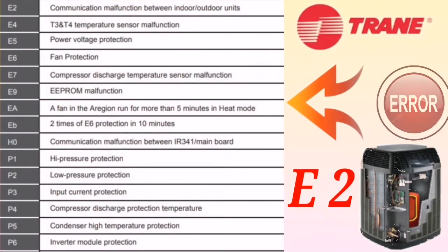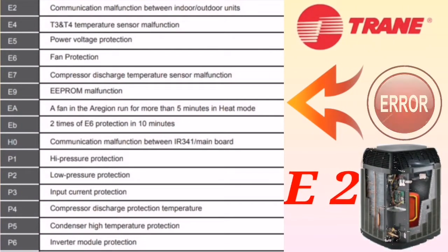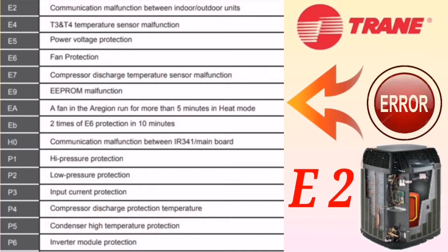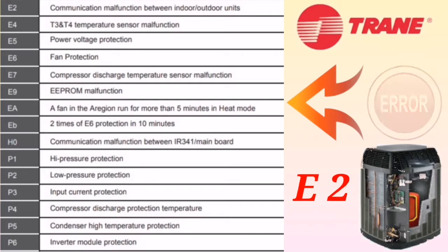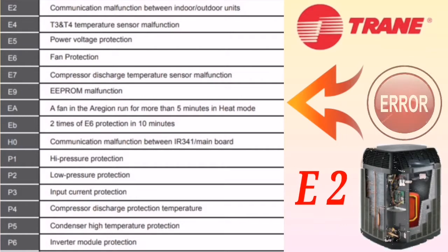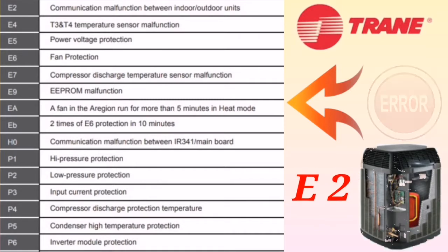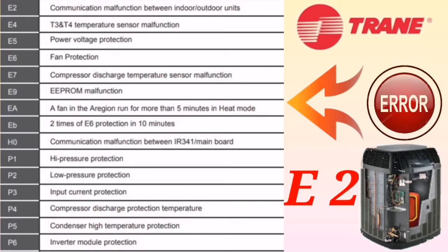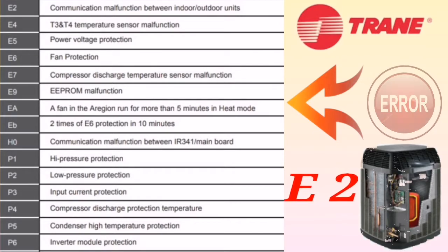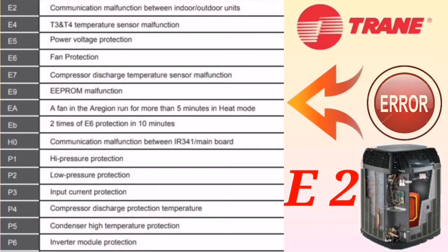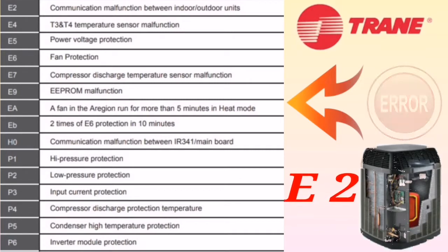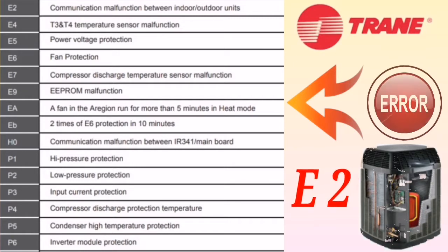The first error code is E2, which means communication malfunctioning between indoor and outdoor unit. First, check the communication cable between indoor and outdoor — if it is broken or loosely connected, reconnect it properly. If the problem persists, remove the communication cable from the outdoor unit, start the indoor unit, and check the communication cable voltage, which should be between 13 to 24 volts. If it is not in that range, the indoor PCB is faulty and needs to be changed. Similarly, if the outdoor PCB is not giving 13 to 24 volts, the outdoor PCB needs to be replaced.